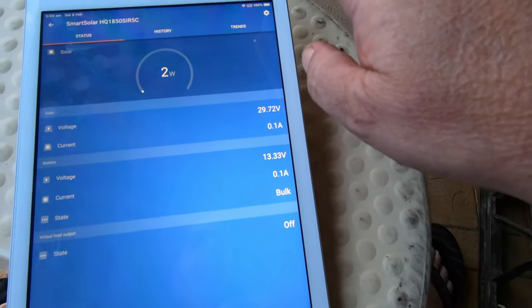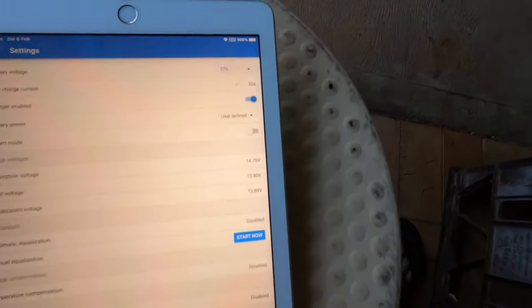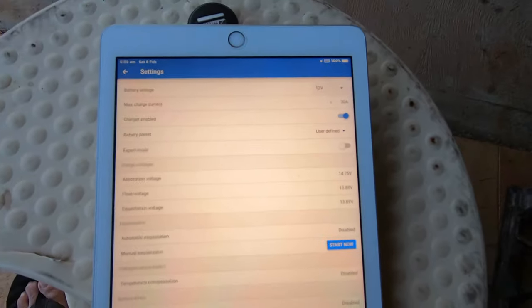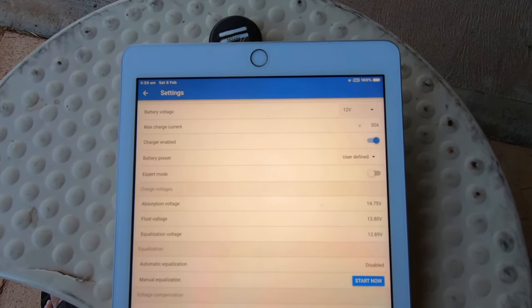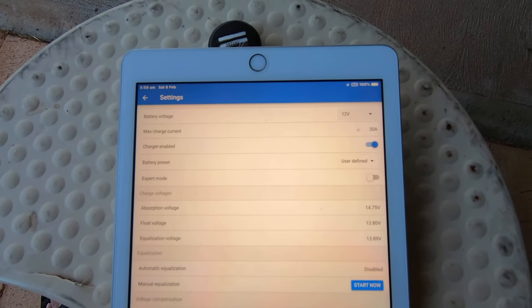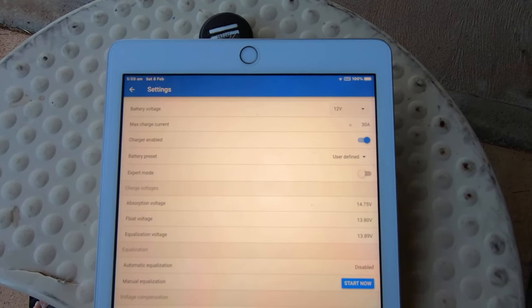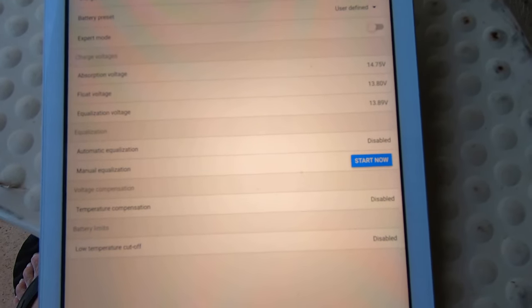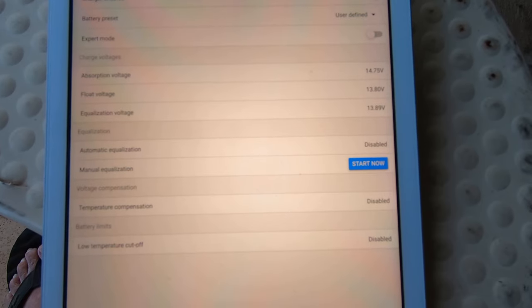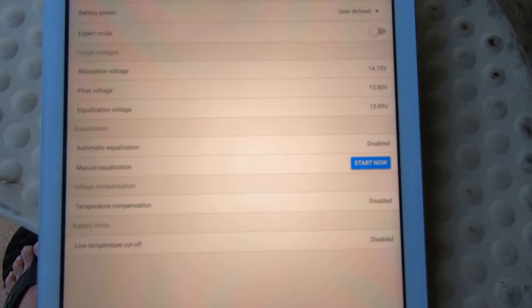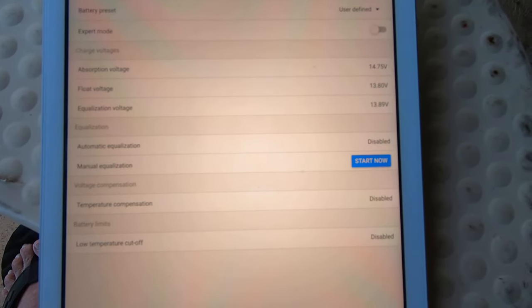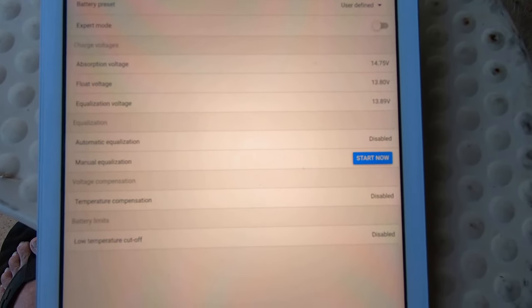Now we go into the settings and we go to battery. Battery voltage 12 volt, maximum current that's the maximum current I've set at 30 amps. Charger enabled, battery presets user defined. Then I've got all my absorption voltage. That battery will take, well its maximum is 14.8.